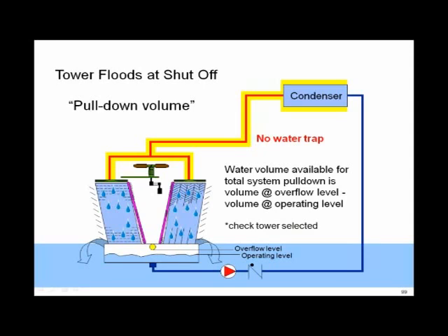It drains into the tower, goes out the overflow, and it floods the parking lot, and you blame the tower manufacturer. Well, you can't do all that overhead piping and all that condenser water piping above the tower and have it all drain out. The sump's just not big enough and it doesn't make a lot of sense. Now, what do you do about this?